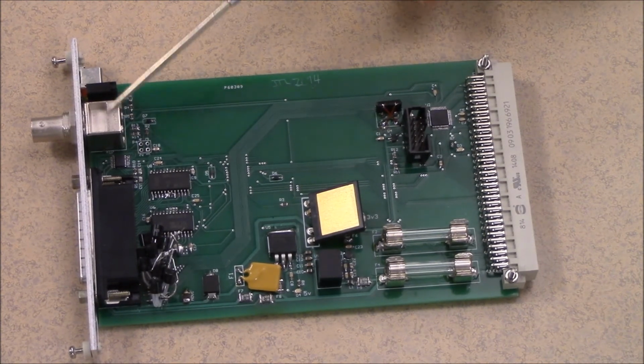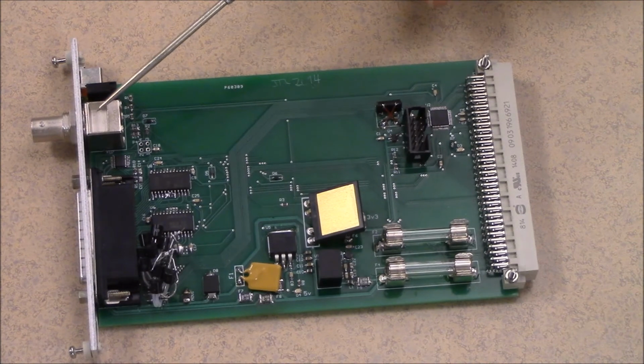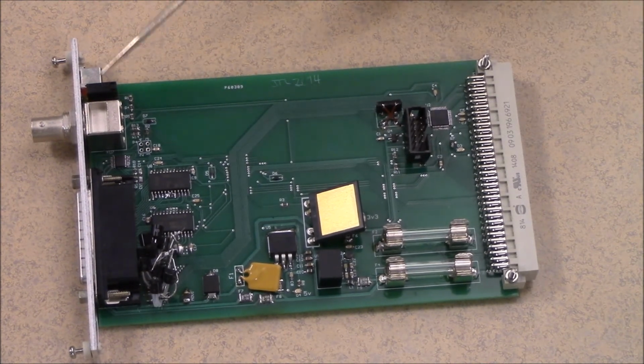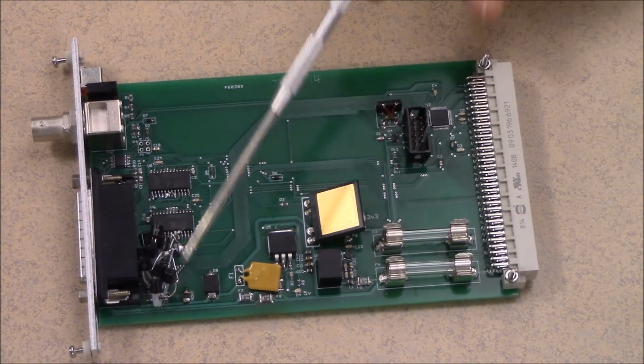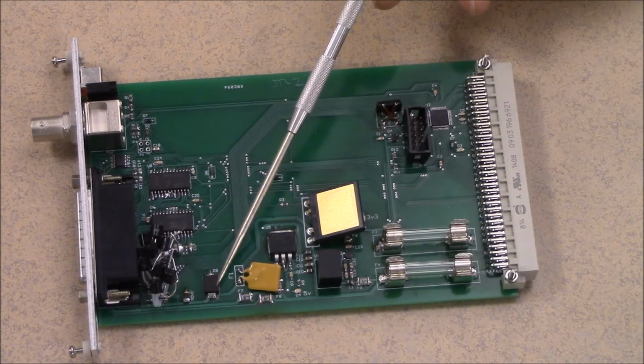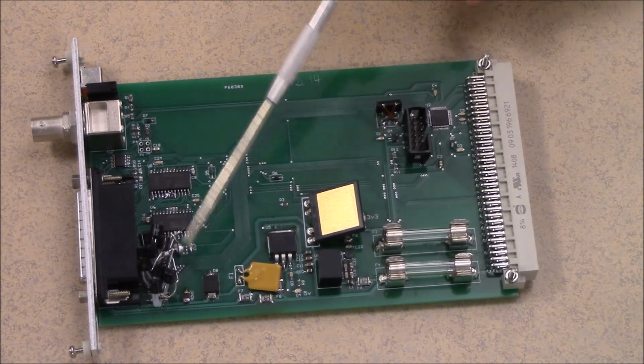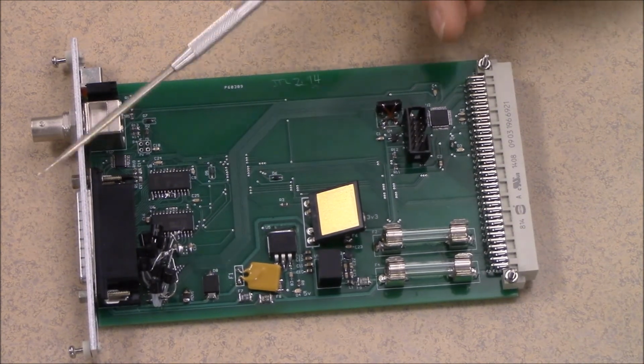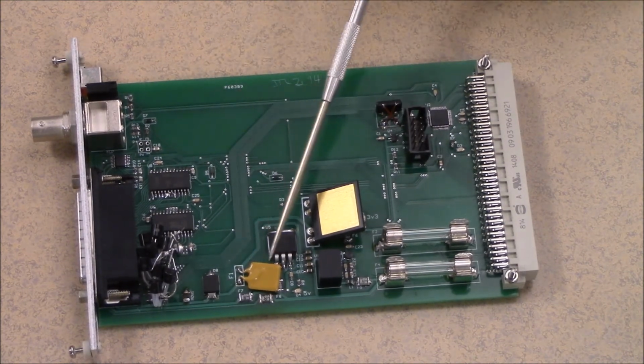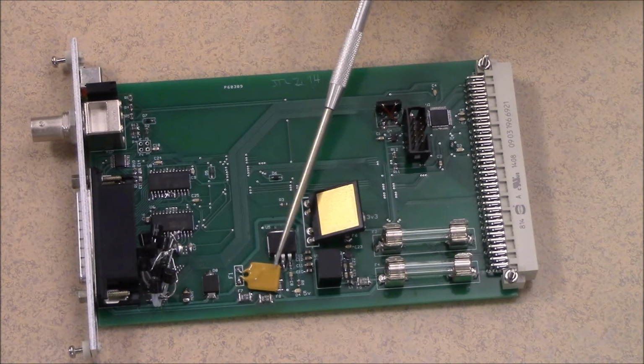This is another BNC connector, except it is used as an input for an emergency stop, which disconnects the loads. Here again is a traffic light LED to demonstrate state. And here is a metal oxide varistor and a very large TVSS diode to protect the switched 24-volt line that is interrupted by the e-stop from transients from the relays and other loads. It's also protected by a polyfuse here in yellow.